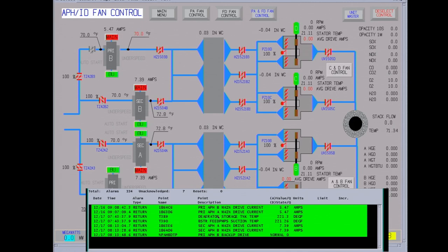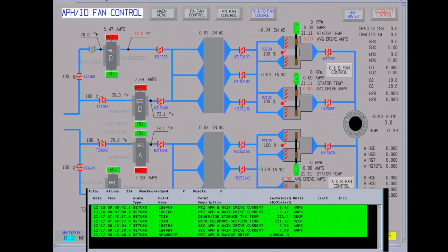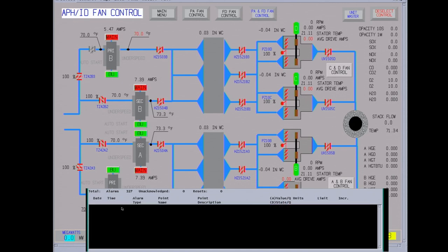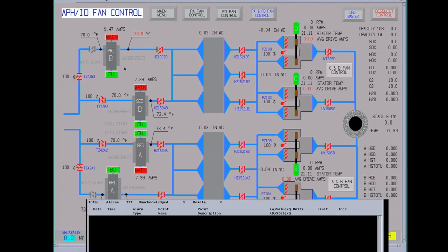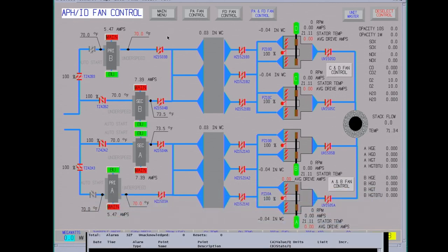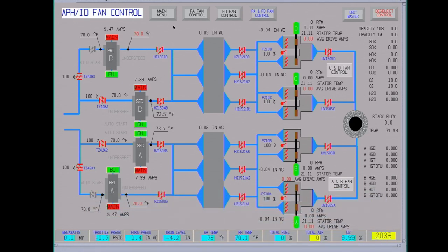Okay, backup in auto. Now we have all the air preheaters are running. Our alarm screen, we've got our drive currents came in high amps. Deaerator storage tank temperature is coming up. Let's acknowledge them. Usually don't have more than about six alarms on the screen. Need to pay attention to what's coming in. A lot of times important alarms will get lost in the sea of alarms you get.